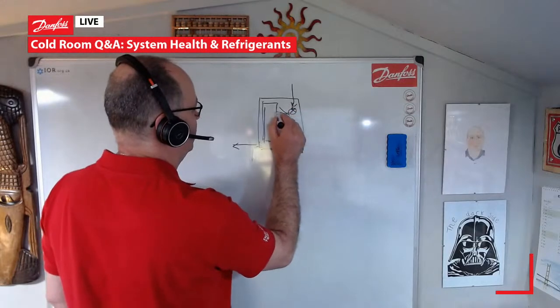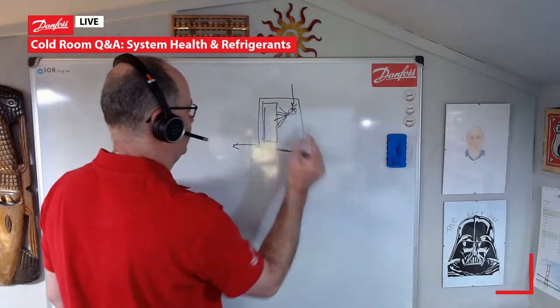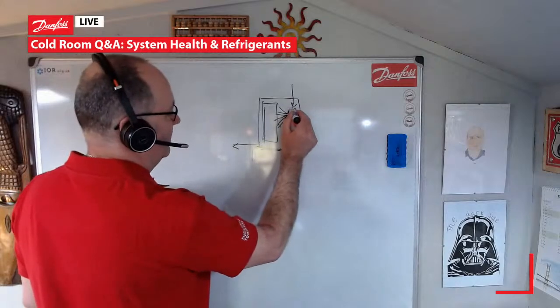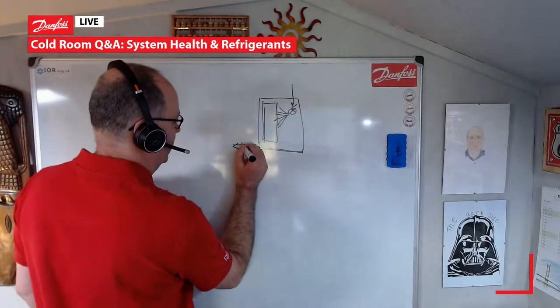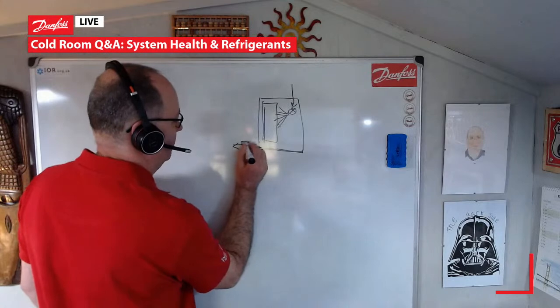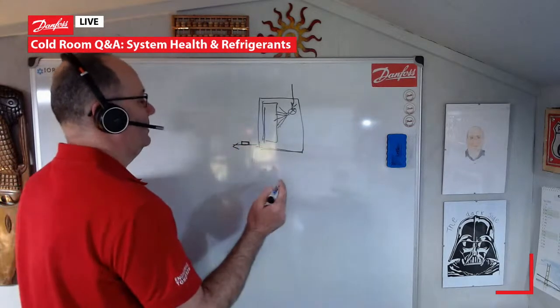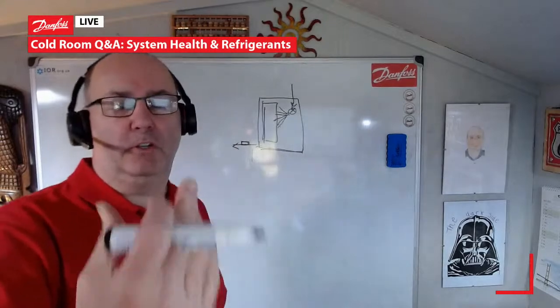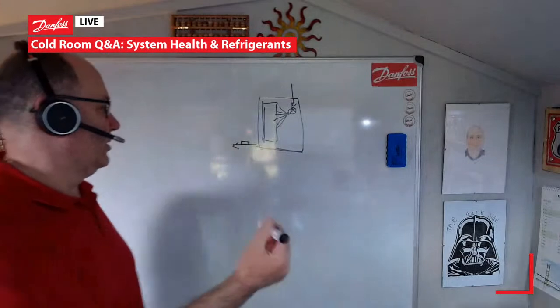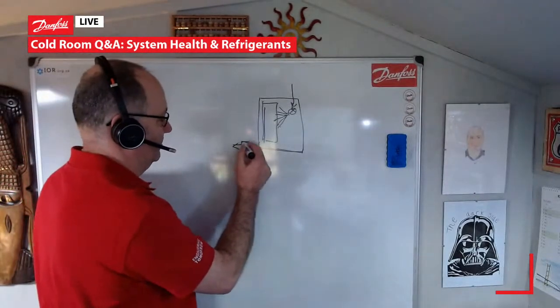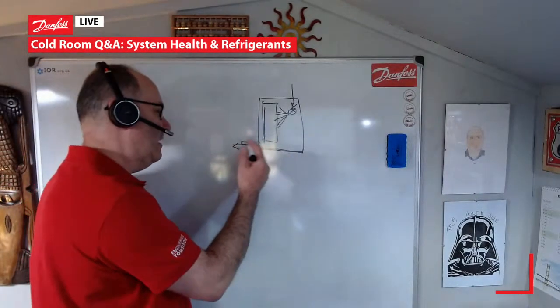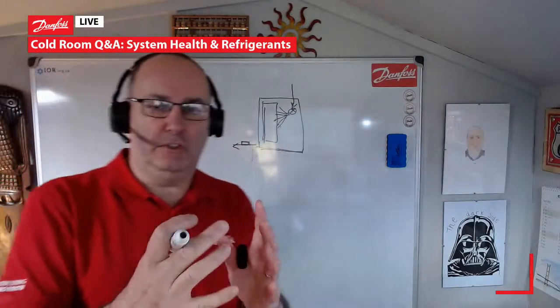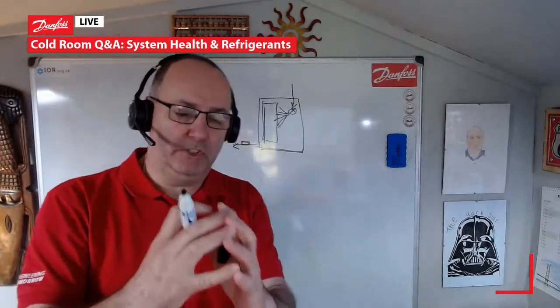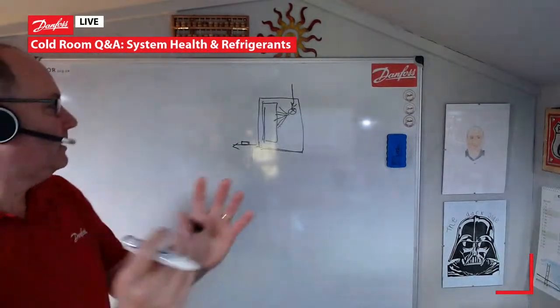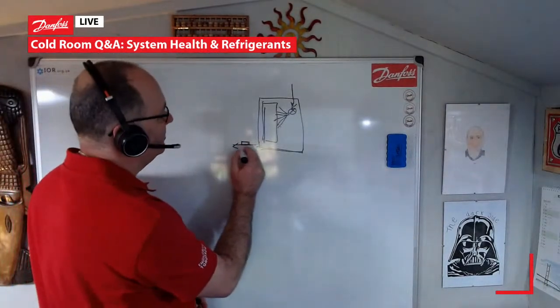And then that feeds our coil with our distributor. Now, what we need from our expansion device is we need our sensing bulb, as we said, on the suction line, good thermal contact. Please use the bulb strap that comes with the valve. Don't use tie wraps, electrical tape, anything like that, because the bulb strap that straps the bulb onto the suction line actually does it with enough force to deform the bulb itself, so it gives it a slight flat spot and gives a really good thermal contact.